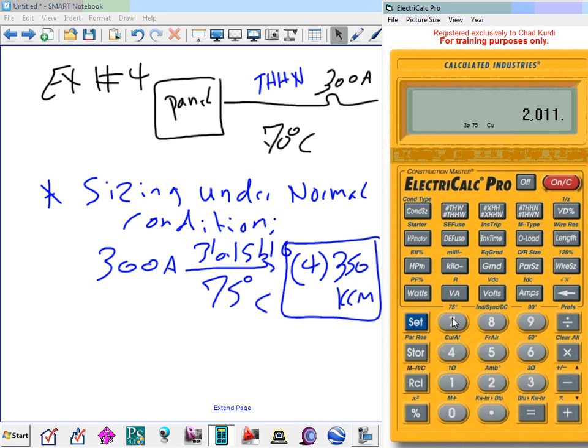I'm telling the calculator, go use 310.15(B)(16) based on 75. Why 75? Because the amps are higher than 100. So I default to where? 75. And I'm not derating. I am not derating yet. I'm not doing any derating. Okay, so I set my calculator. The rest is piece of cake.